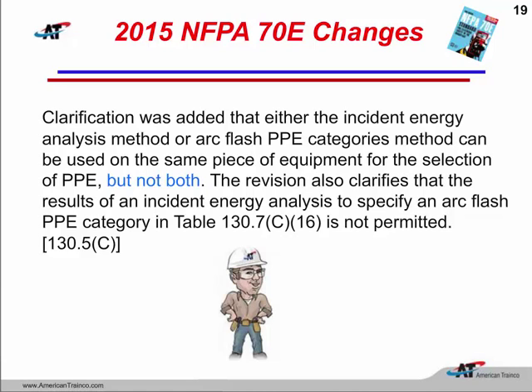We can do the full-blown analysis. Usually we'll have a team of engineers come in. They will be using software that is going to collect a lot of data. It's going to determine the fault current at each piece of equipment, the clearing time of the overcurrent device. So that's the analysis method. Or we could use the table method. They gave us a choice of doing this all the way since 2004. So we can use either method, but we cannot use both methods on the same piece of equipment.